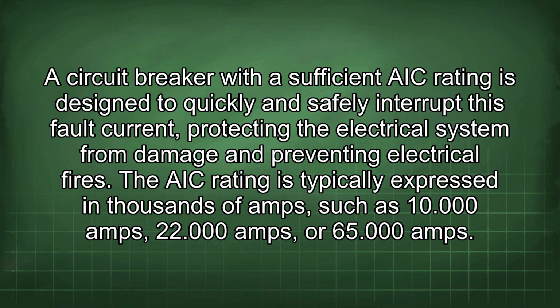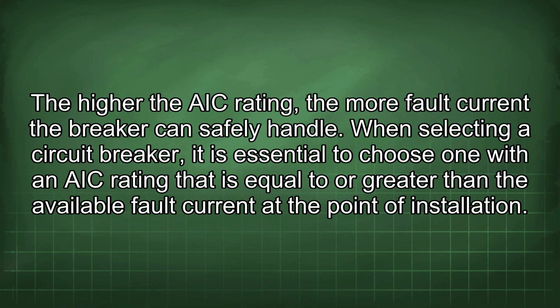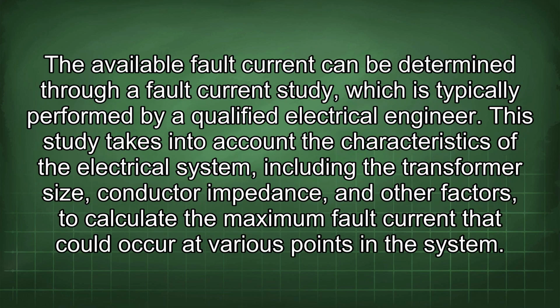The AIC rating is typically expressed in thousands of amps, such as 10,000 amps, 22,000 amps, or 65,000 amps. The higher the AIC rating, the more fault current the breaker can safely handle. When selecting a circuit breaker, it is essential to choose one with an AIC rating that is equal to or greater than the available fault current at the point of installation. The available fault current can be determined through a fault current study, which is typically performed by a qualified electrical engineer. This study takes into account the characteristics of the electrical system, including the transformer size, conductor impedance, and other factors to calculate the maximum fault current that could occur at various points in the system.